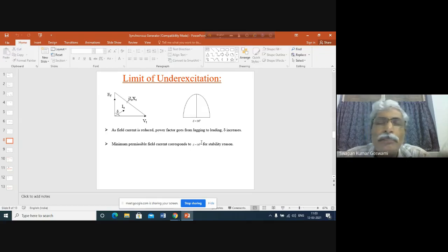This source of reactive power will be delivering reactive power to the system. During heavy load conditions, this reactive power helps you maintain the normal system voltage. They supply some reactive power, and the additional reactive power required is supplied by the generator. If some additional is required, maybe there are installed capacitors, some fixed capacitors and some switched capacitors.